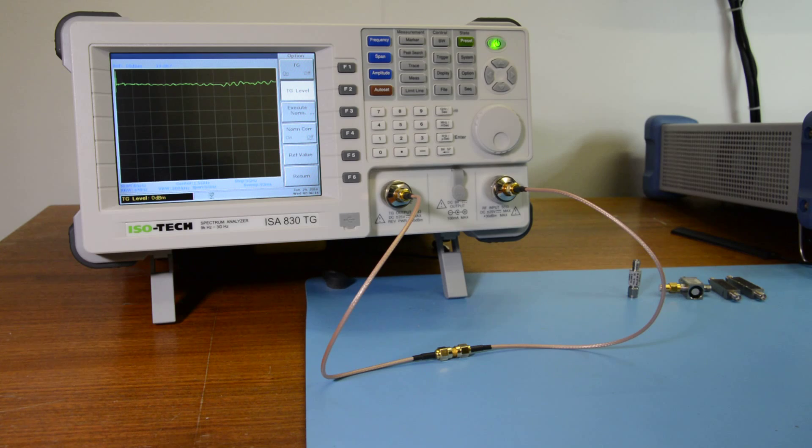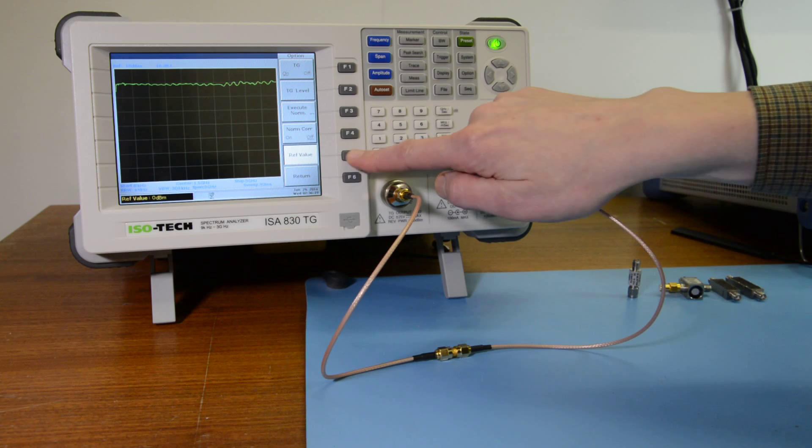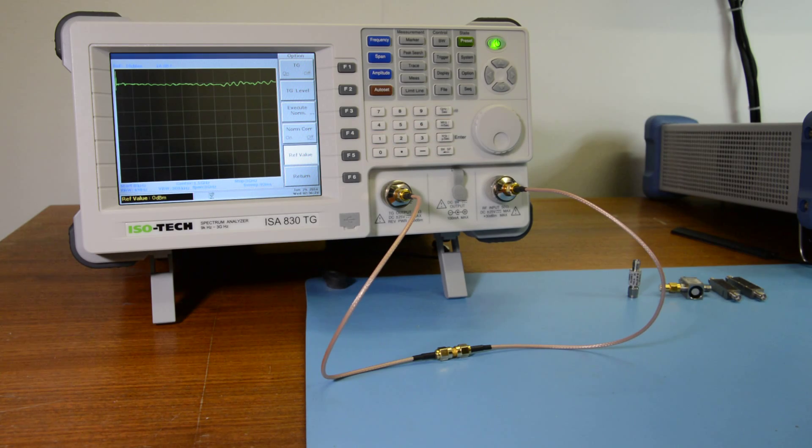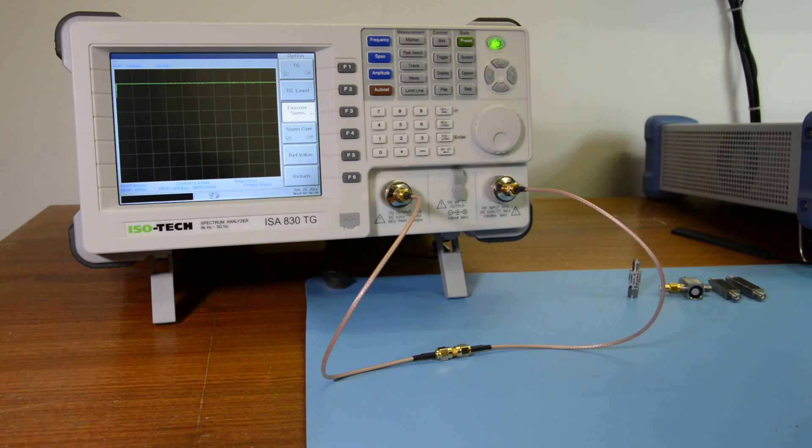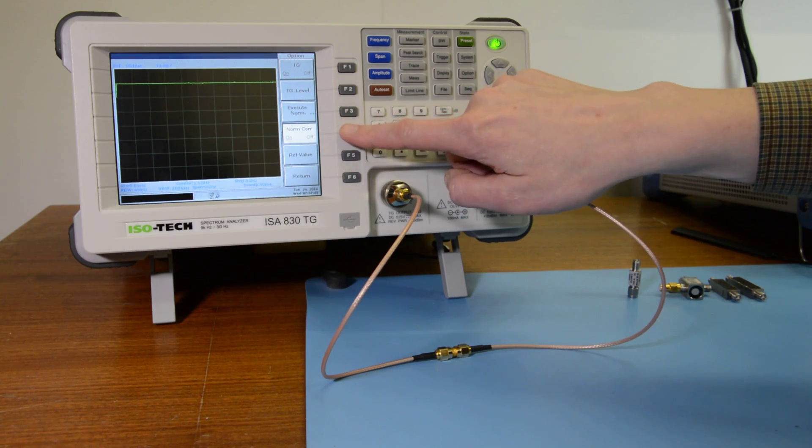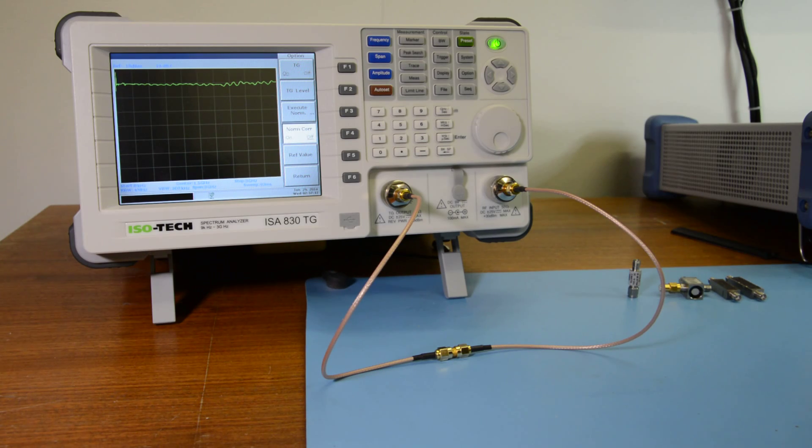Now to do that, we can set the level of the signal that will be used for performing that task. That's selected by pressing F5 for the reference value. We can see that that's set to 0 dBm, which is fine certainly in this case. So then we can press F3 to execute normalization and then F2 select yes, and we can see the result there with correction in place. Now if we press F6 to return, we can check there that normalization correction is turned on. We can toggle this between on and off by pressing F4 just to see the effects again without that correction in place. If we turn it back on.